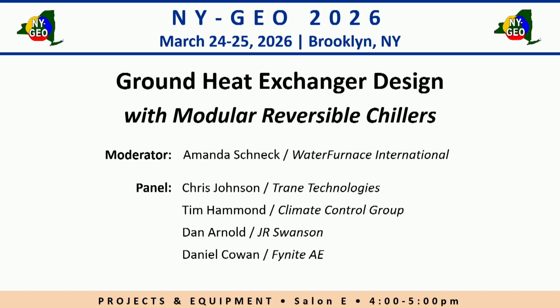So you're always lifting from like 70 to 140, or you're lifting from 40 to 70, right? So that again goes into the control sequence that the engineer of record needs to provide, saying that I want this many chillers running at these times so that you can minimize that lift. Now, talk about a large building: 60 stories, and we have our plant on 10 of the stories. So you have that core cooling need in the middle of the building for 50 stories, right? So that's putting heat into the loop.